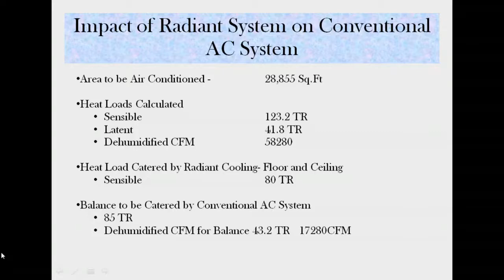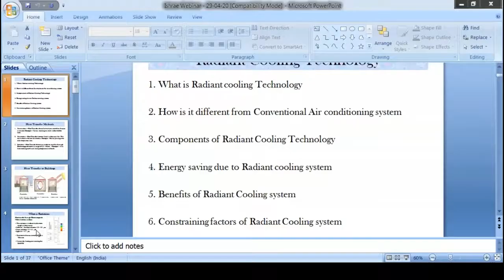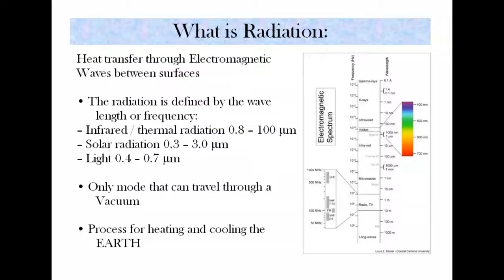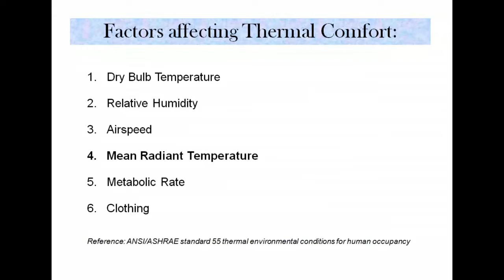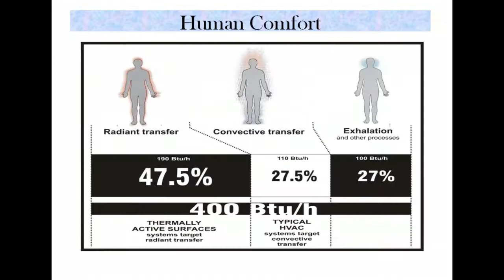Okay. So, sir, can we add a fresh air system in this radiant cooling? Yeah, you can have a dedicated outdoor air system. In the radiant system, what they do is they have a combination of the conventional system as a dedicated outdoor air system with a heat recovery. You calculate the humidity requirement, you calculate the pressure requirement, and whichever is higher, that air is supplied as dedicated outdoor air in that particular area with a heat recovery system. If you look at the Infosys building in Hyderabad, they don't have the conventional system; it is a dedicated outdoor air system in combination with the radiant system. And you can have a conventional system with recirculation air, and you can add pressure to the conventional system.